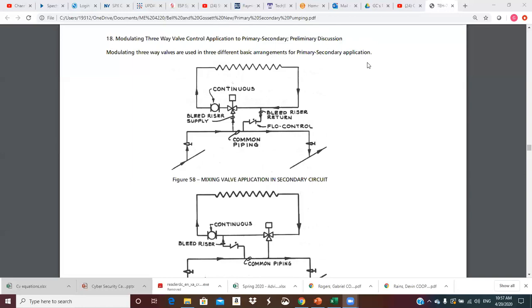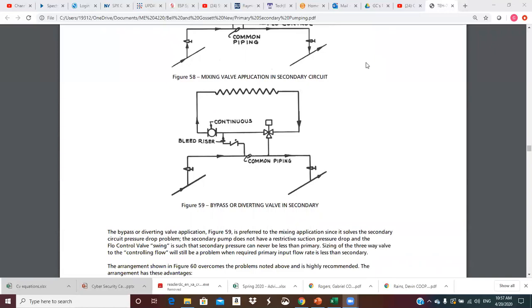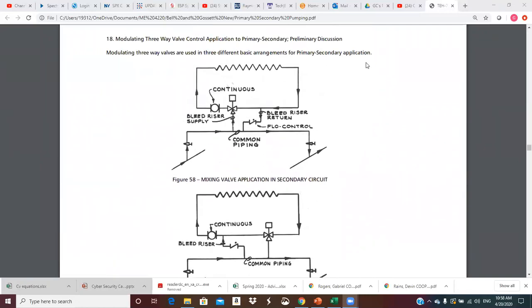As you can see in figure 58, the control valve can basically block off the return port from the secondary and force all of the crossover bridge flow up into the secondary, or a portion of it. There could be some mixing — whatever came up the bleed riser would go down the return bleed riser. The common pipe is located in the crossover. Here's a bypass instead of a mixing valve — a diverting valve in the secondary. The diverting valve has one inlet and two outlets, while the mixing valve has two inlets and one outlet.